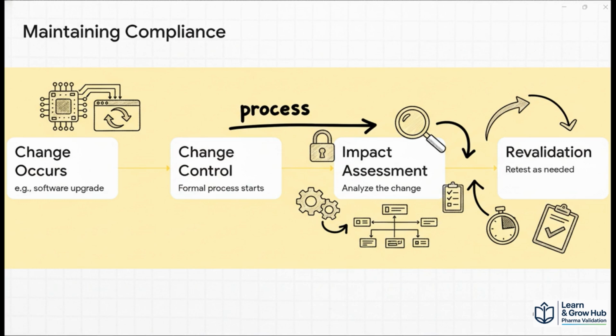Finally, we must consider change control and revalidation. Validation does not end after the PQ is finished. If you modify the PLC logic, replace a sensor, or upgrade your SCADA, you must follow a process. You need a change control and an impact assessment. This might lead to partial or full revalidation. This ongoing maintenance is critical for passing audits by the US FDA, MHRA, and WHO.